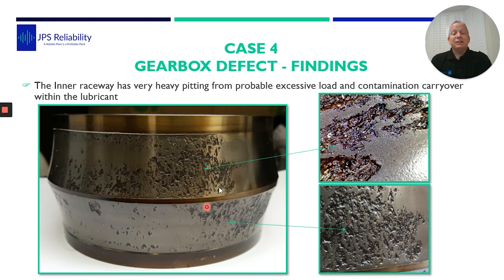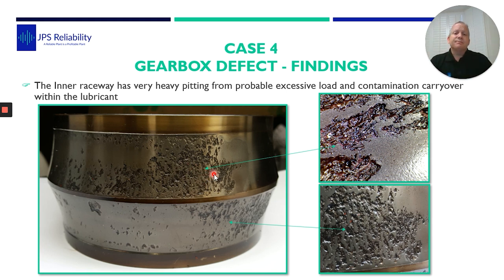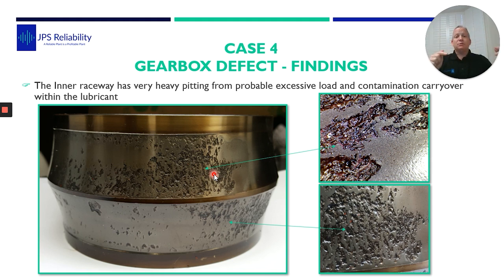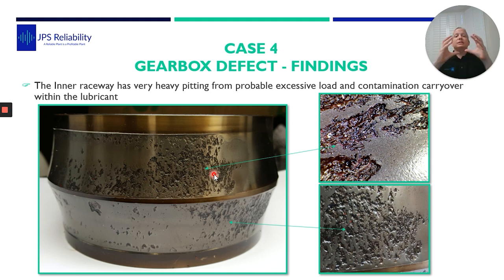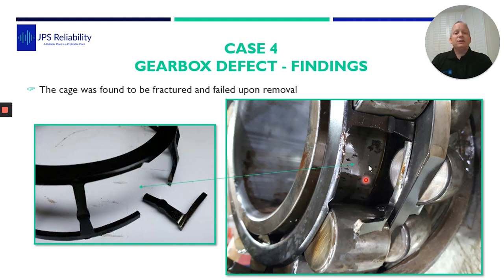What we found on both shafts was an area of spalling. Also, as the bearing was failing it was being over-rolled within the lubricant. We marked up all the bearings — drive end, non-drive end, top, bottom, and importantly where the weights were. It turned out that at the furthest point of the weight swing, where you get the highest load and shock, it was always the same location — because the weights are bolted to the shaft and don't move. That same point on the inner race is under the highest stress all the time, and on the opposite side you could also see the damage starting in the race.